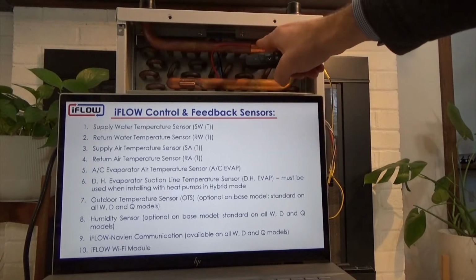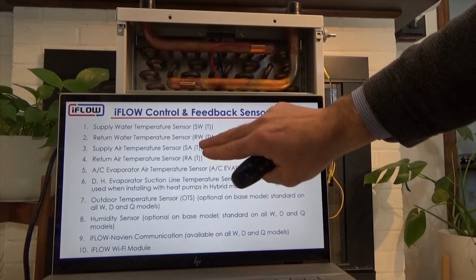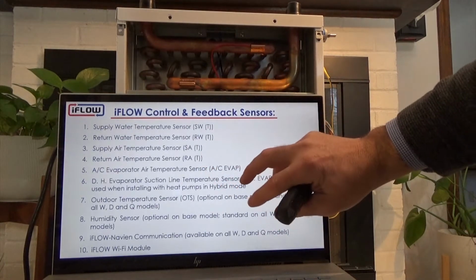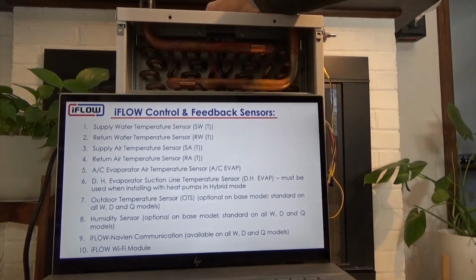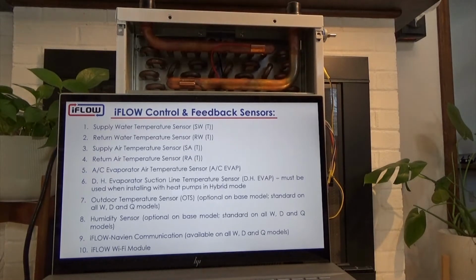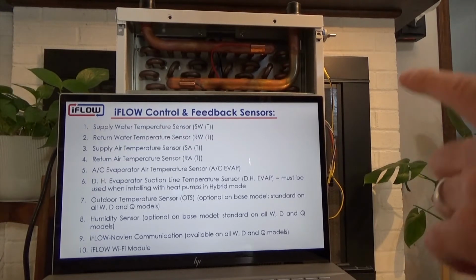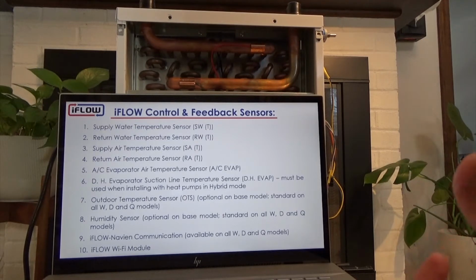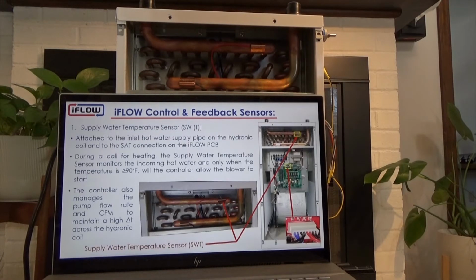We have, as I mentioned, the supply water temperature and the return water temperature. We have a supply air temperature and return air temperature sensor. We have the AC evaporator temperature sensor that I showed you earlier. We have the DH evaporator temperature sensor for heat pumps. We have an outdoor sensor that is always measuring the outdoor temperature and then calibrating the delivery of BTUs on the inside accordingly. We have the humidity sensor, as I mentioned. We have a communication cable that works with the iFLOW Navien. And then we've got our Wi-Fi module. So those are the items we're going to look at. Some are control, some are just wiring, so it's a mix of wiring and control.